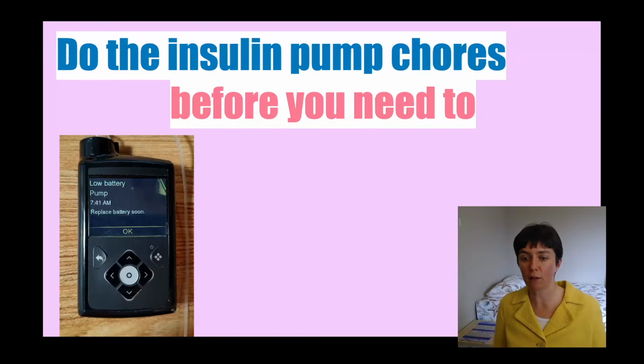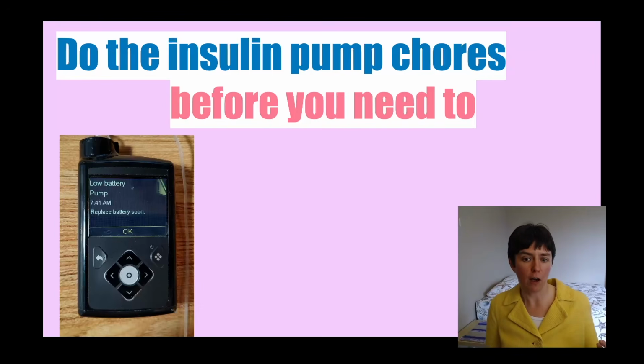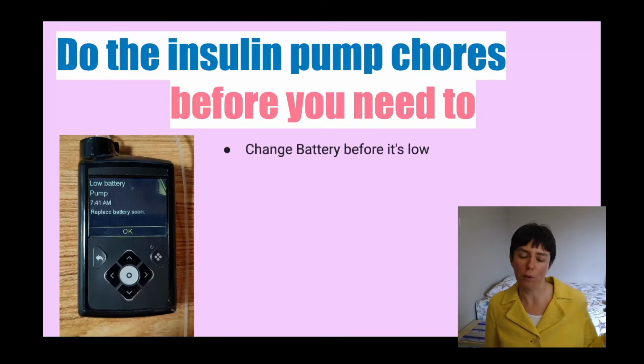So I found that doing the insulin pump chores before you need to is how you are able to sleep through the night and not be interrupted, and not think about diabetes when you don't want to. Most of the different notifications, reminders, and alarms this pump does, you can modify or turn off. However, one notification you cannot disable is the low battery notification. And technology generally works better when the battery isn't low.